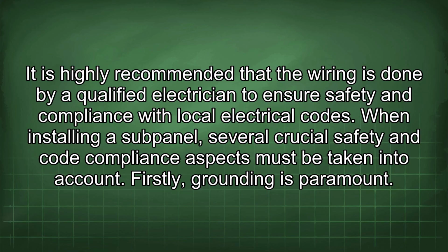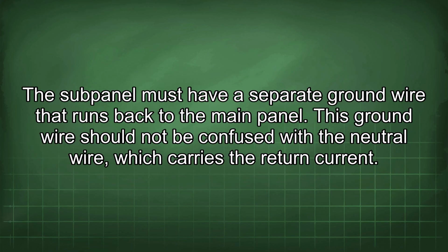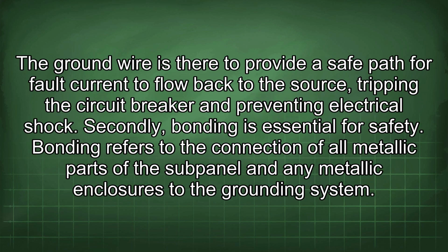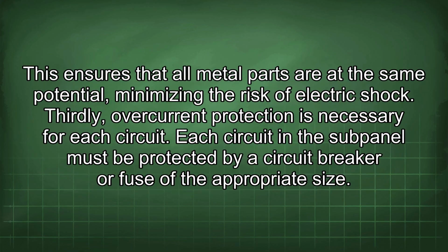Firstly, grounding is paramount. The subpanel must have a separate ground wire that runs back to the main panel. This ground wire should not be confused with the neutral wire, which carries the return current. The ground wire is there to provide a safe path for fault current to flow back to the source, tripping the circuit breaker and preventing electrical shock. Secondly, bonding is essential for safety. Bonding refers to the connection of all metallic parts of the subpanel and any metallic enclosures to the grounding system. This ensures that all metal parts are at the same potential, minimizing the risk of electric shock.